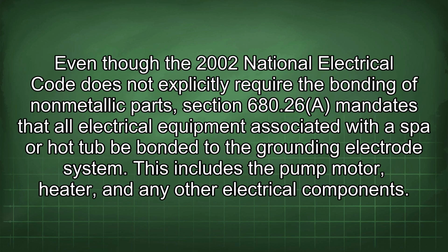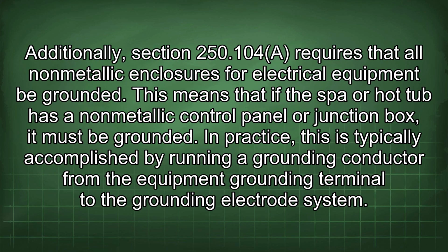Even though the 2002 National Electrical Code does not explicitly require the bonding of non-metallic parts, Section 680.26 mandates that all electrical equipment associated with the spa or hot tub be bonded to the grounding electrode system. This includes the pump motor, heater, and any other electrical components. Additionally, Section 250.104 requires that all non-metallic enclosures for electrical equipment be grounded. This means that if the spa or hot tub has a non-metallic control panel or junction box, it must be grounded. In practice, this is typically accomplished by running a grounding conductor from the equipment grounding terminal to the grounding electrode system.